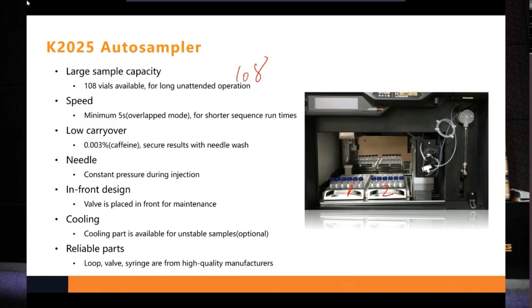And the needle has a patented design to keep constant pressure when performing the injecting action. And the interior and exterior surface of the needle can be washed before and after the injection. And the valve is placed in front for easy maintenance. And the cooling function is optional for unstable samples, especially for the biological samples. And the most important parts of the autosampler, such as loop, valve, and syringe, are from high-quality manufacturers to ensure the performance and stability.